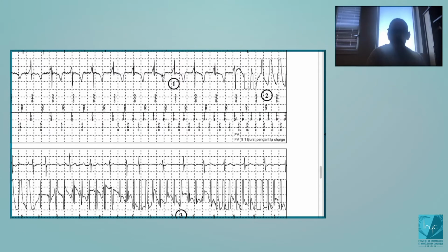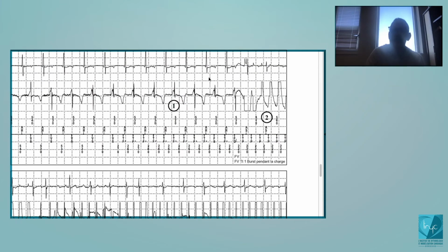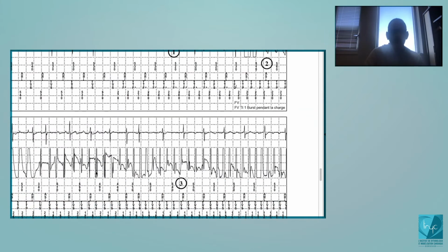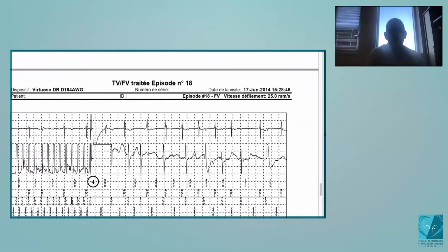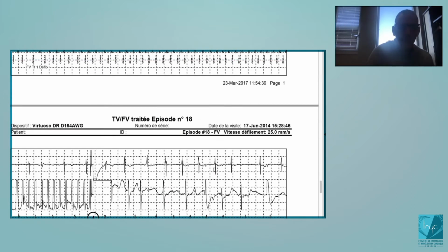So this patient was completely stable, without any episode of ventricular tachycardia or arrhythmia before implantation. You implant the device, T-wave oversensing, and then the first burst is delivered on the T-wave, and you induce a very fast and polymorphic arrhythmia, okay, and life-threatening. Luckily, this patient does not have a high threshold, so at the end, the shock which is delivered is efficient with reduction of the arrhythmia, okay.